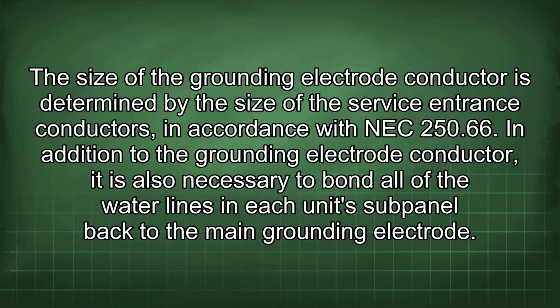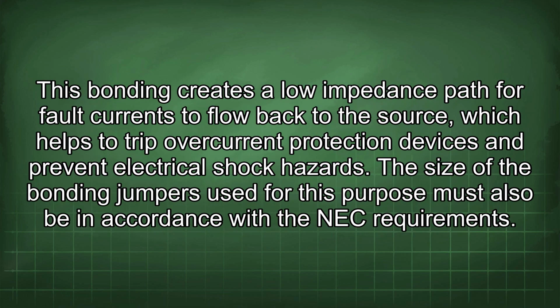each unit subpanel back to the main grounding electrode. This bonding creates a low impedance path for fault currents to flow back to the source, which helps to trip overcurrent protection devices and prevent electrical shock hazards. The size of the bonding jumpers used for this purpose must also be in accordance with the NEC requirements.